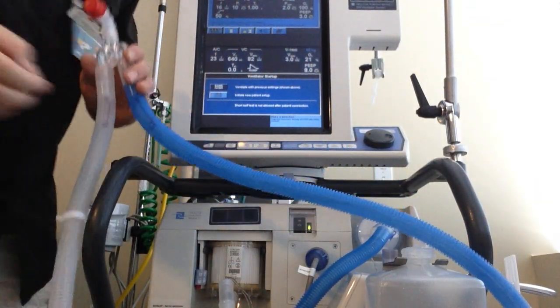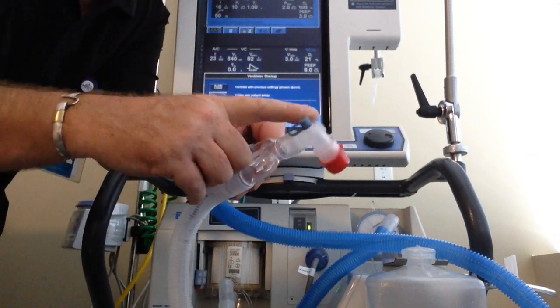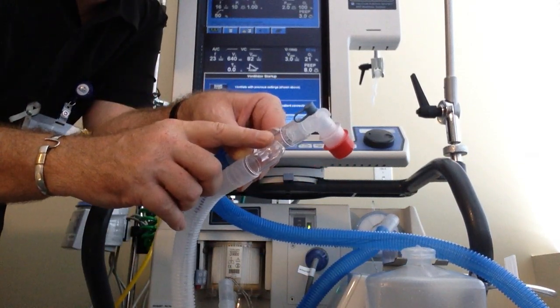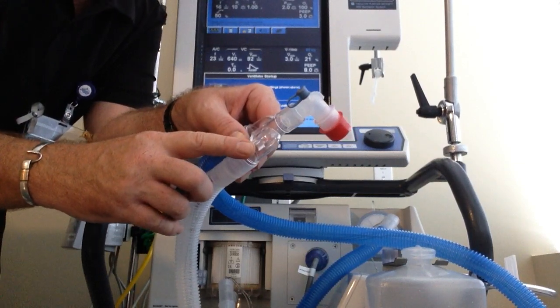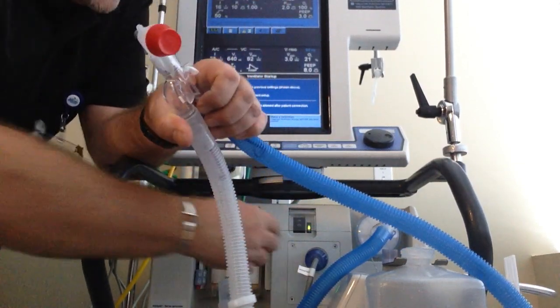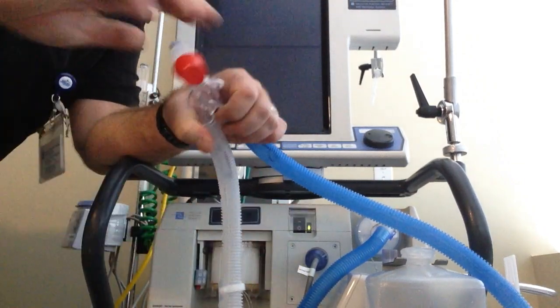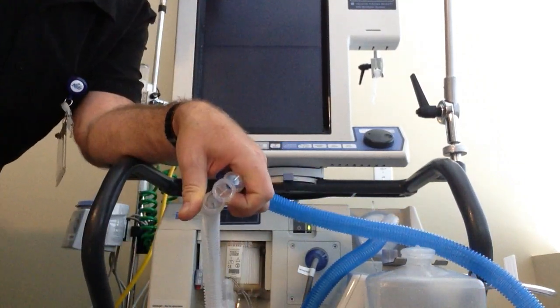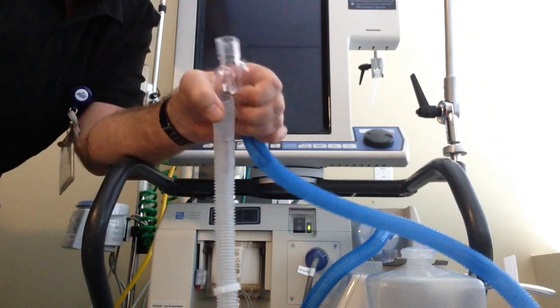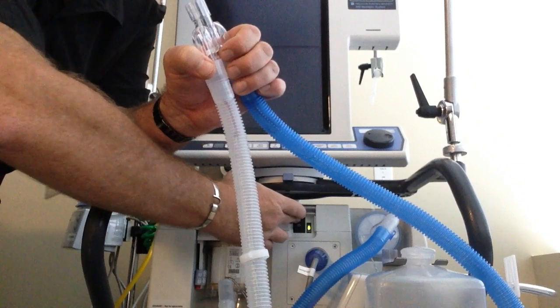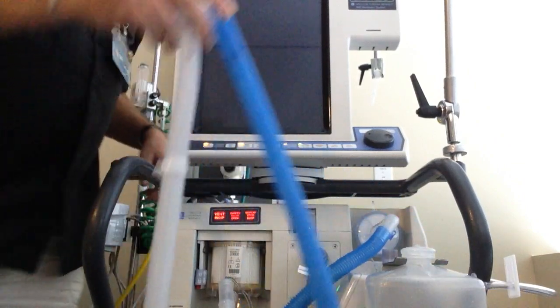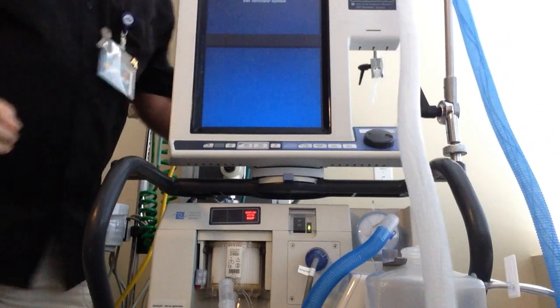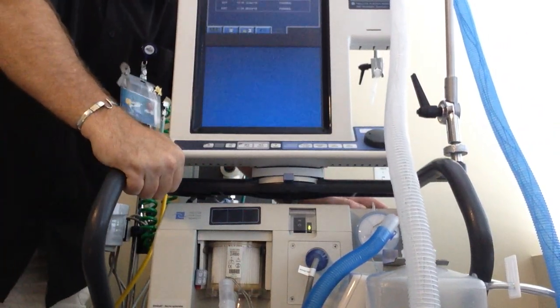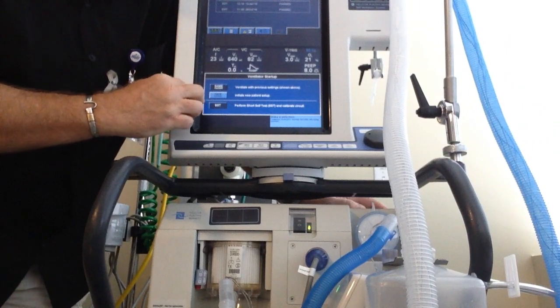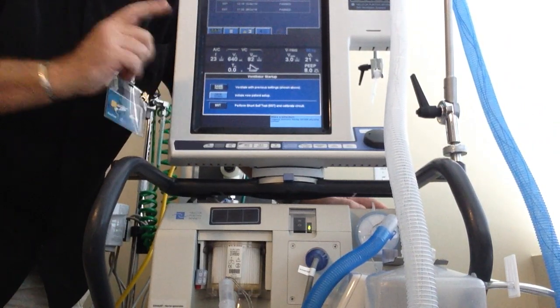Well, the Puritan Bennett 840, if you turn it on with the Y blocked, it will think that it's going on back onto a patient and will not allow you to do the SST. So you must turn it back off, unblock the Y. I'm going to lay this to the side, and then turn the ventilator back on. The circuit will not be pressurized, and the ventilator will then allow you to do the pre-use test. You see the last box down here? I will show it to you better in just a second.